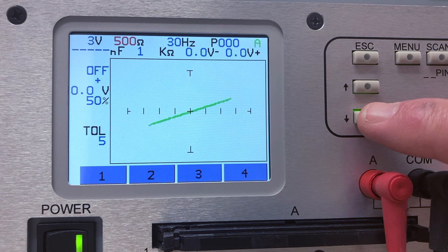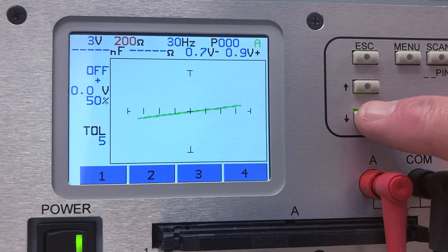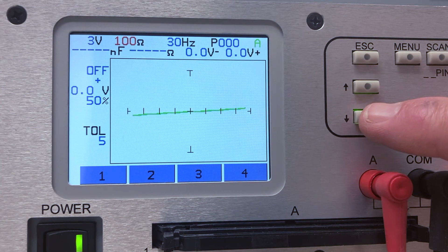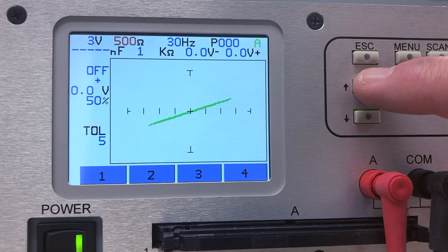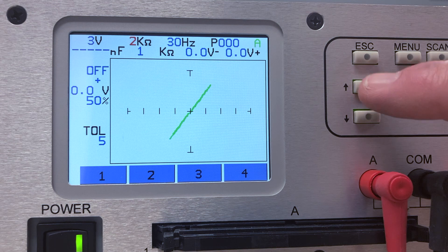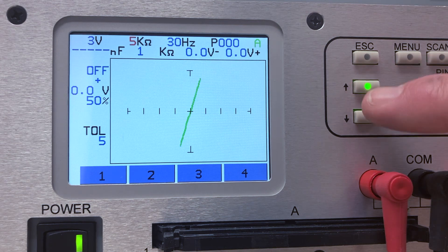Resistive signatures display an angled linear response that is affected by the component value and the range being used by the tracker. In general terms, you want to try and set the tracker resistance range to match the value being tested.